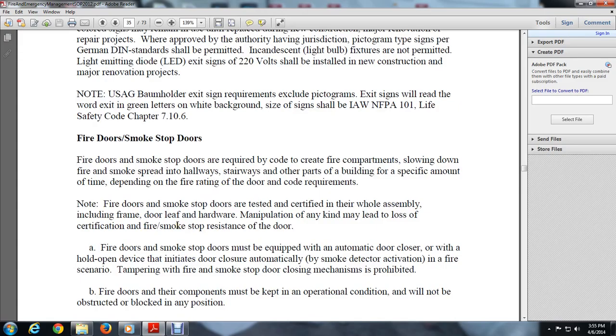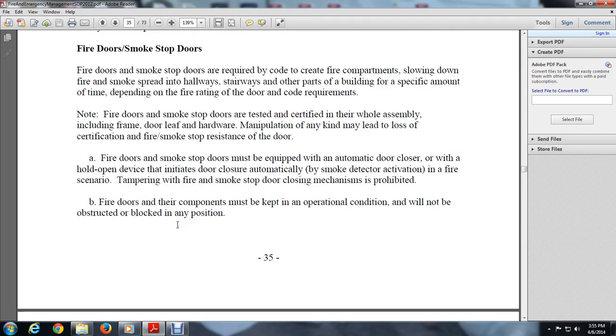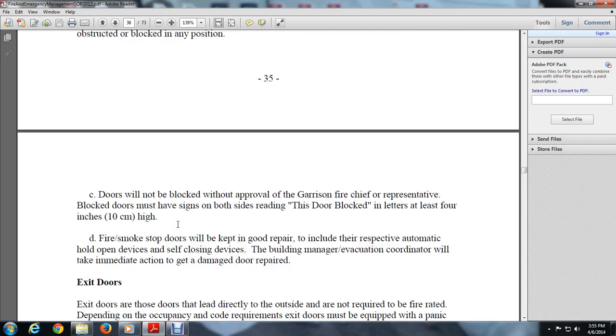Fire door and smoke stop doors must be equipped with an automatic door closer or other hold-open device that releases the door closer automatically upon smoke detector activation in a fire scenario. Tampering with the fire or smoke stop door closing mechanism is prohibited. Fire doors and their components must be kept in operable condition and will not be obstructed or blocked in any position. Doors will not be locked without approval of the Garrison Fire Chief's representative.